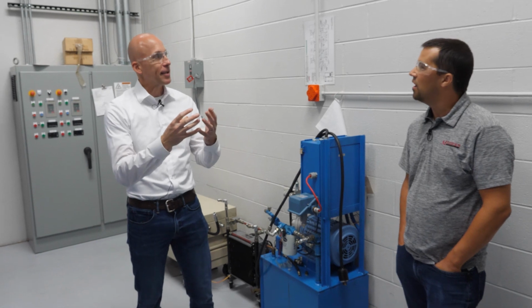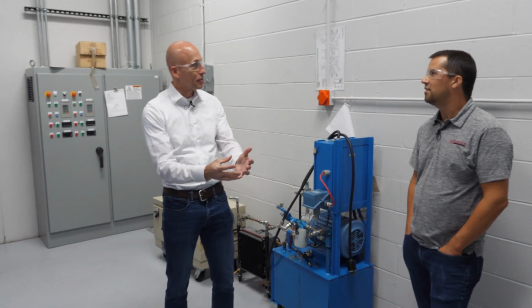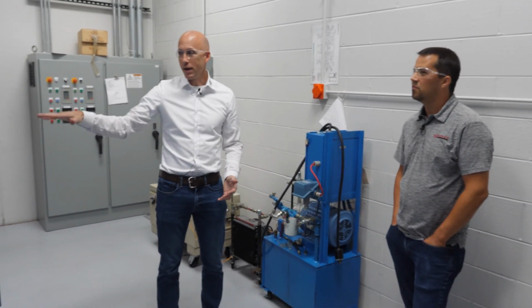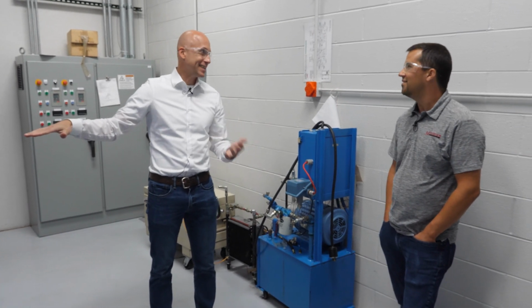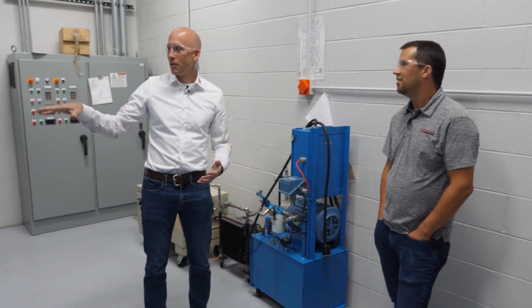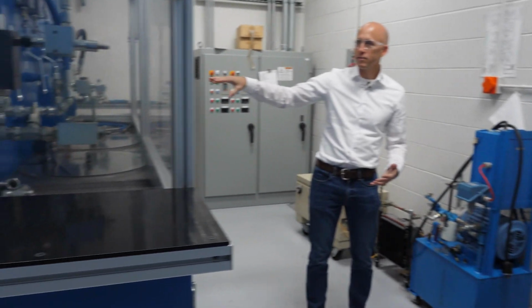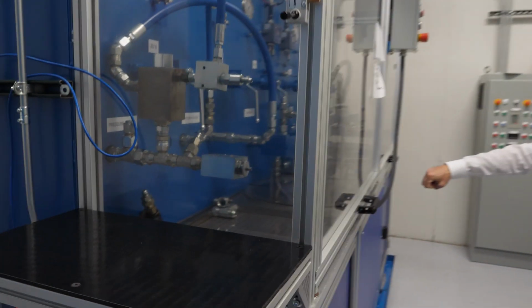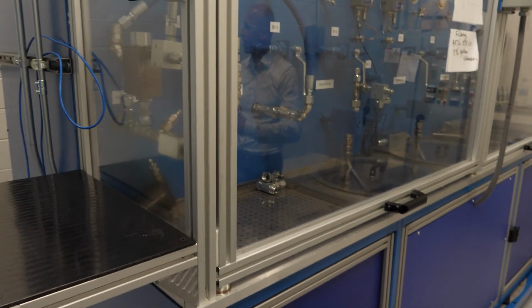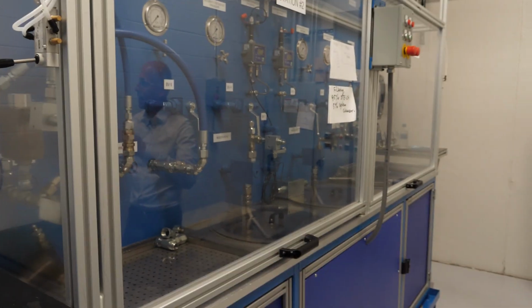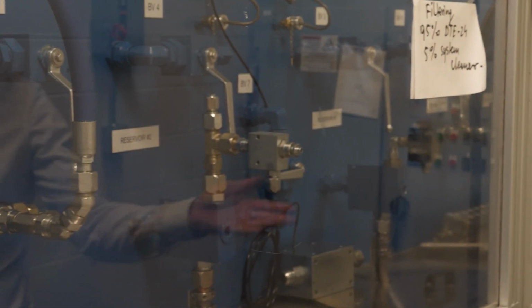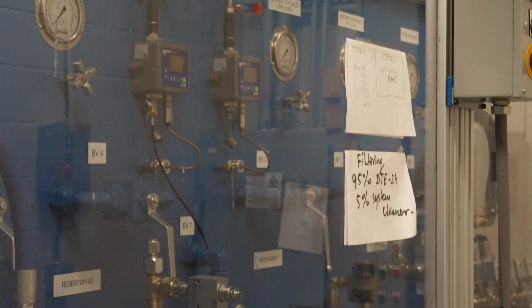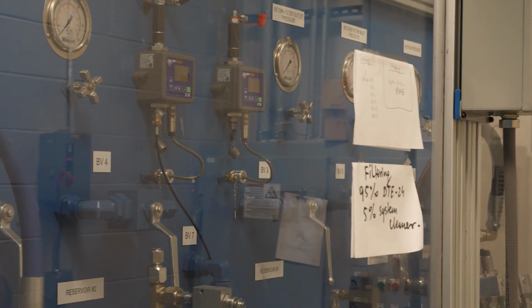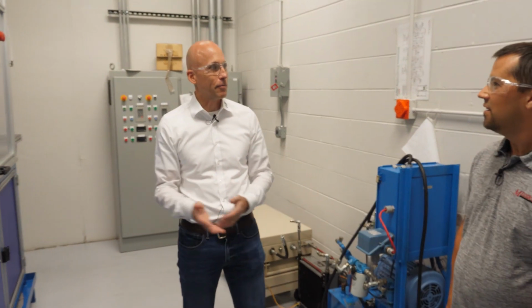While we have to send very clean product to our OEM customers, it has to survive in even contaminated oil. So what we do here is we take our products and introduce contamination on purpose, and we run the valves. We'll turn them on and off. We'll keep running them until we see the actual limitation, like when do they fail. And then when customers come to us and ask how it will operate in this kind of environment, we're able to tell them.